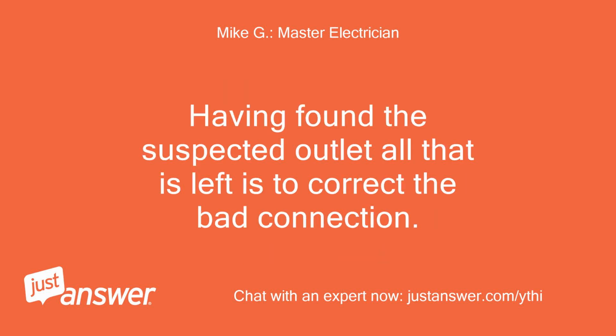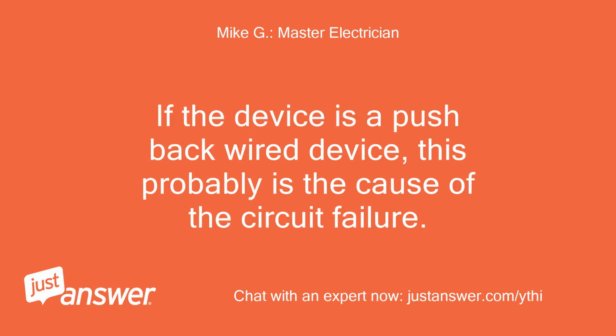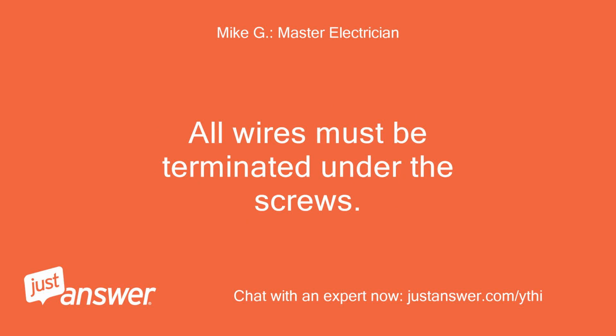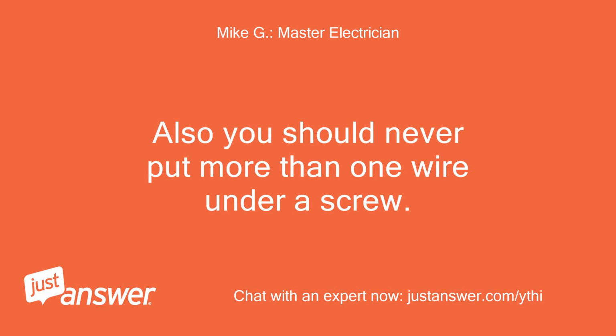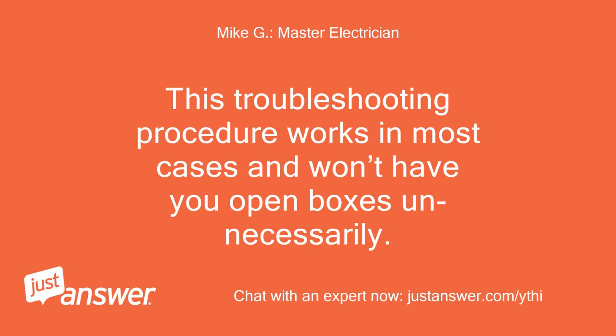Having found the suspected outlet, all that is left is to correct the bad connection. If the device is a pushback wire device, this probably is the cause of the circuit failure. All wires must be terminated under the screws. Also, you should never put more than 1 wire under a screw. This troubleshooting procedure works in most cases and won't have you open boxes unnecessarily.